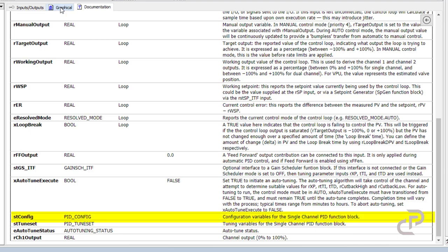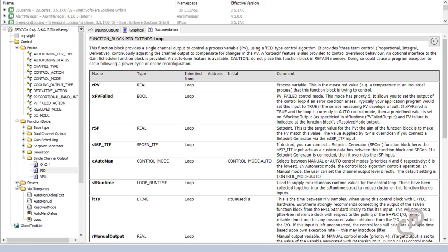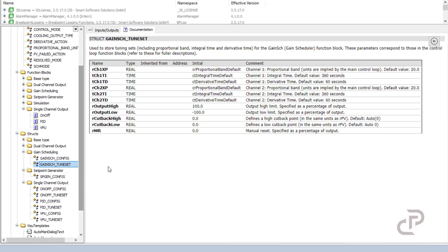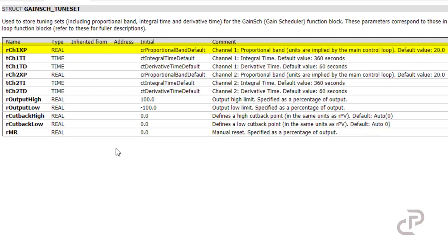st_config is the configuration variable of the PID control, and st_tuning is used for tuning variables. If I click on the structure folder and then gain scheduling, you will see the whole setting for the tuning. Take into account that the first parameter is proportional band, and it has a reverse ratio to proportional gain. The next parameters are integral time and derivative time. If you increase these times, you get a smaller gain for the integral and derivative, so they also have a reverse ratio.